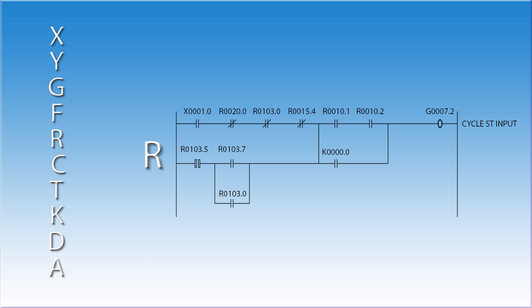The R addresses are free and there are thousands of them. You use these to keep track of what is going on in the ladder. When you look at a ladder diagram, you will find that the vast majority of addresses are R's. Allen Bradley uses the B address for this function. There are a few of the R addresses that FANUC has grabbed for specific operations in the ladder. These are usually in the R9000 range. We discuss these in the advanced ladder logic course.